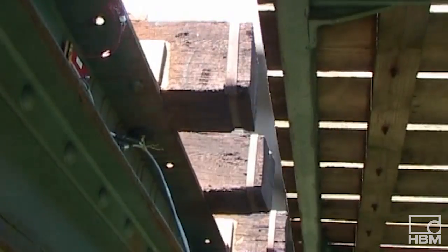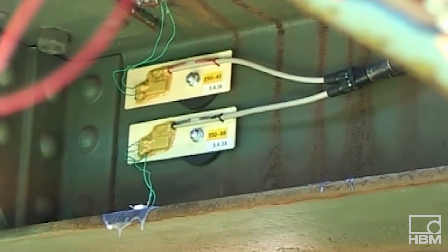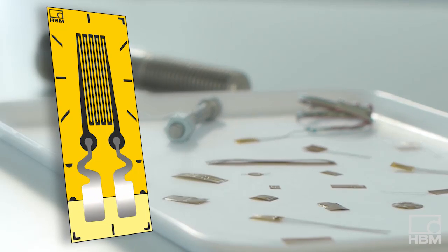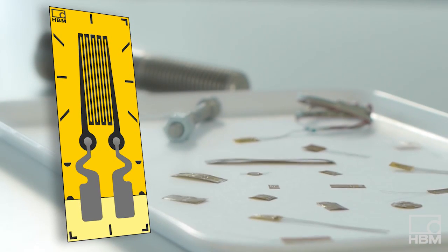For dynamic applications with a very high varying load, we recommend strain gauges with strain relieved solder points which guarantee the optimal isolation of the cable forces from the strain gauge.